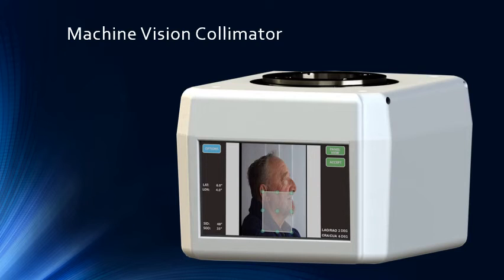Utilizing four independent shutters to automatically position the radiation beam, the MVC ensures the area of exposure always remains within the confines of the active area of the detector, eliminating the need to physically link the components. A visual display provides real-time video of the patient, with a shaded area appearing on the video image to indicate the location and size of the radiation beam with respect to the patient. Additionally, the angle and inclination of the X-ray source is displayed to the operator on the display as well.